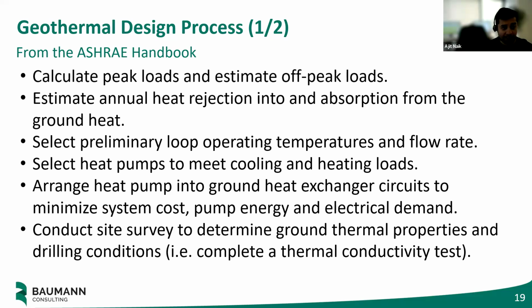Definitely not good enough to finalize your design. You absolutely have to do a test bore at your site. Cross-town geologic conditions can change dramatically. Even a couple blocks down the road, you might run into something totally different. So even if you have a geothermal test bore at 500 feet, 10 blocks away, and you're trying to do the same thing, you still have to do a bore yourself.